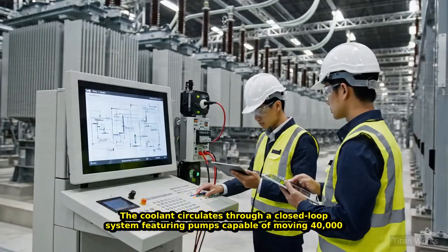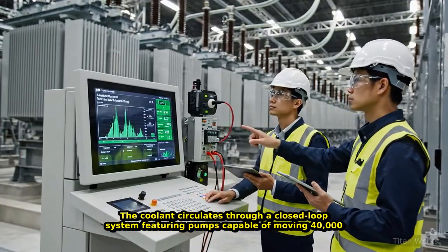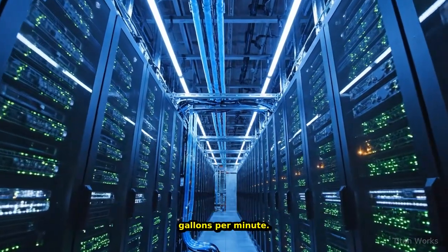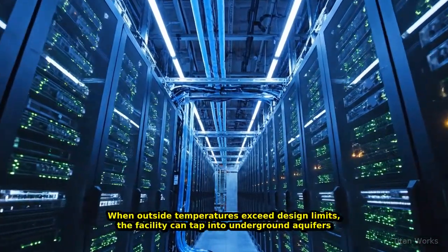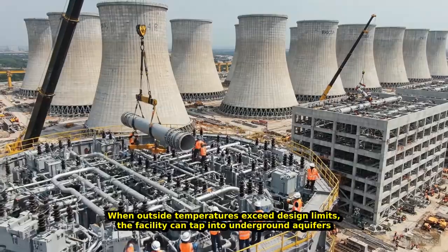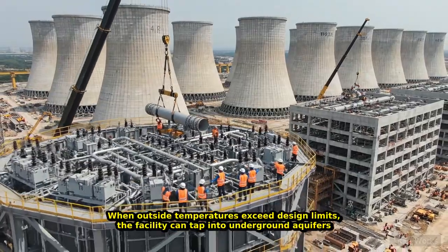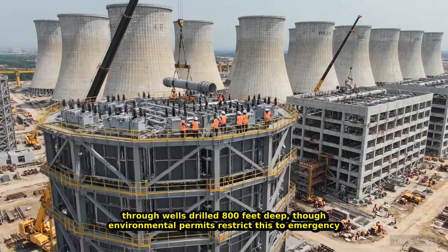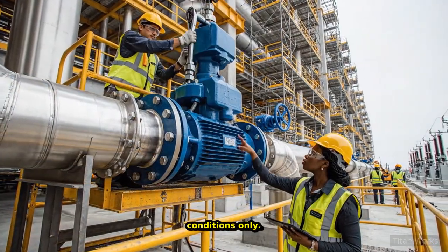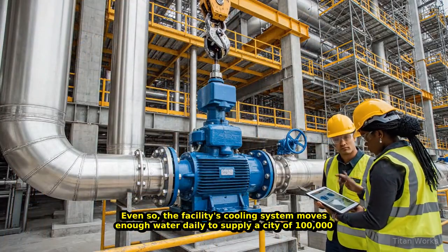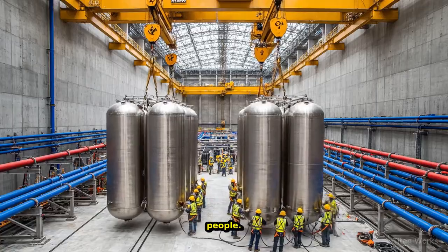The coolant circulates through a closed-loop system, featuring pumps capable of moving 40,000 gallons per minute. When outside temperatures exceed design limits, the facility can tap into underground aquifers through wells drilled 800 feet deep, though environmental permits restrict this to emergency conditions only. Even so, the facility's cooling system moves enough water daily to supply a city of 100,000 people.